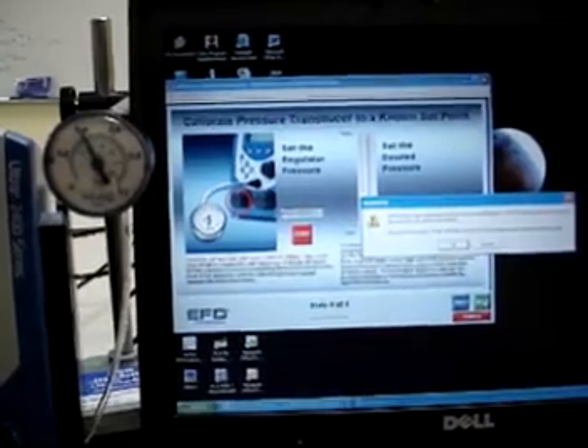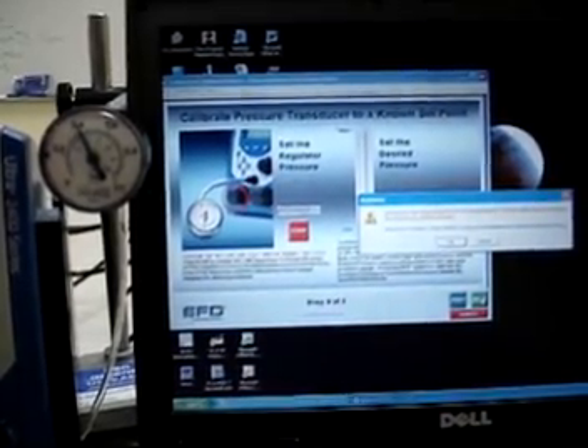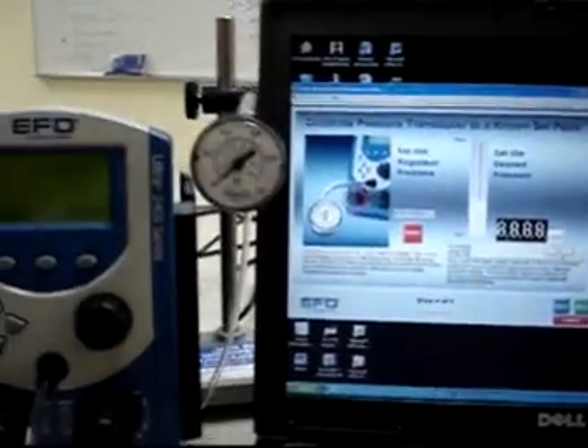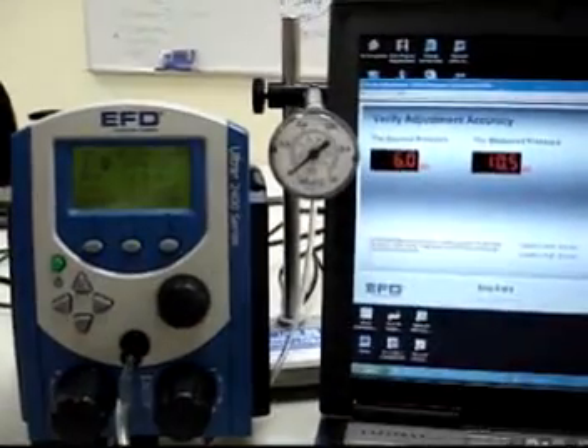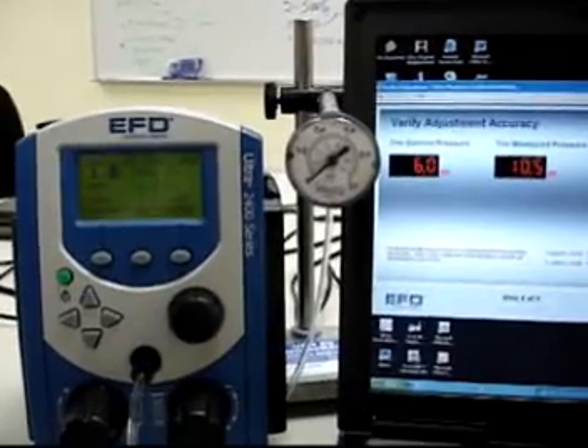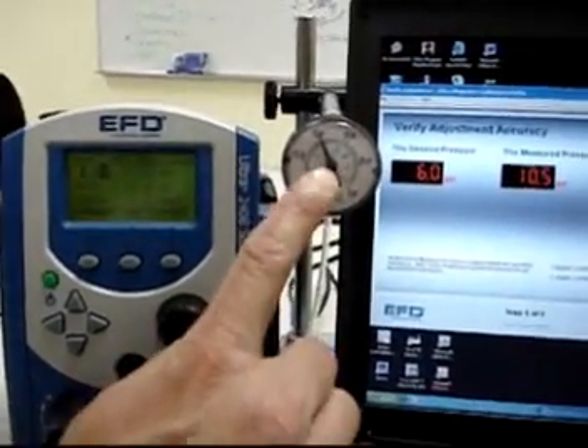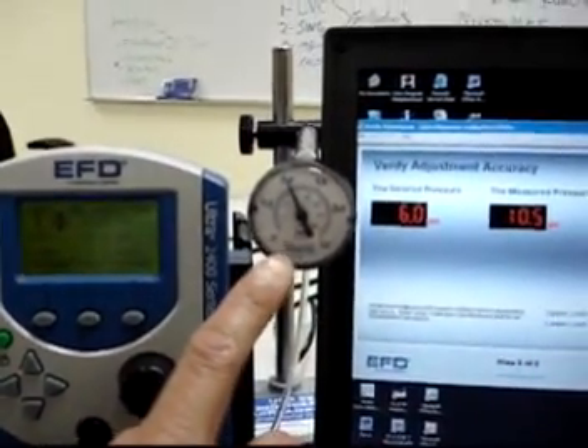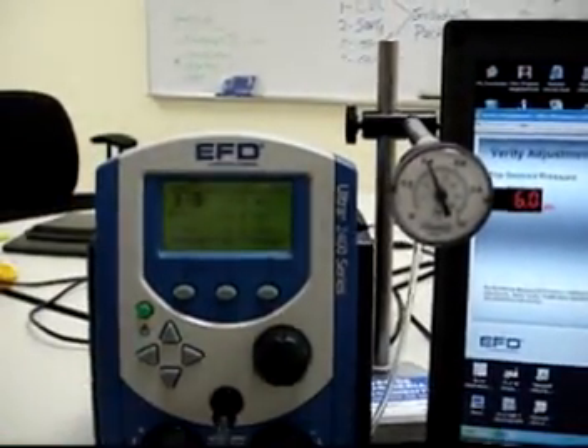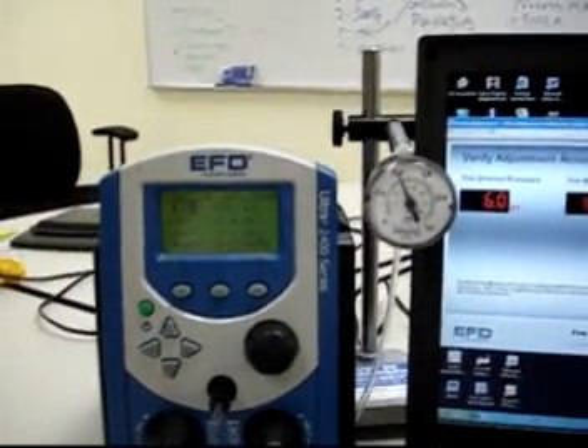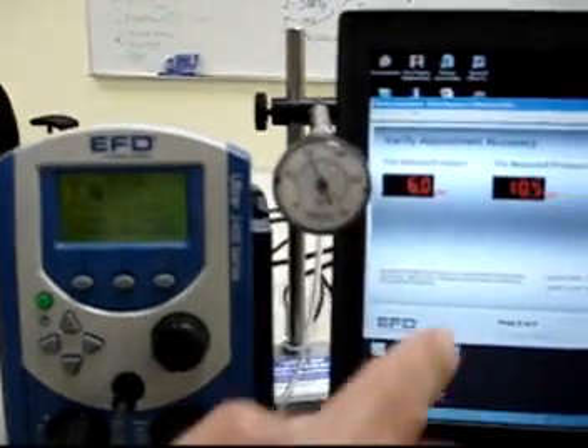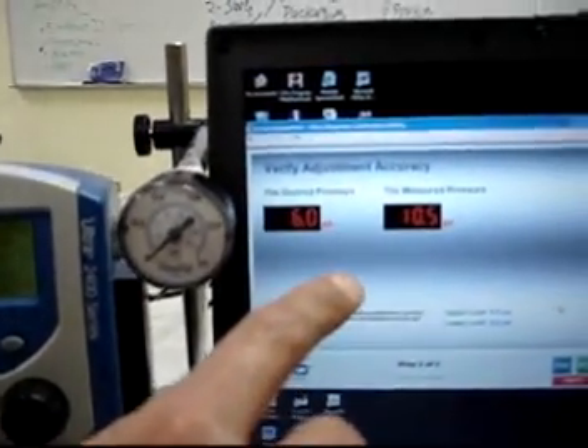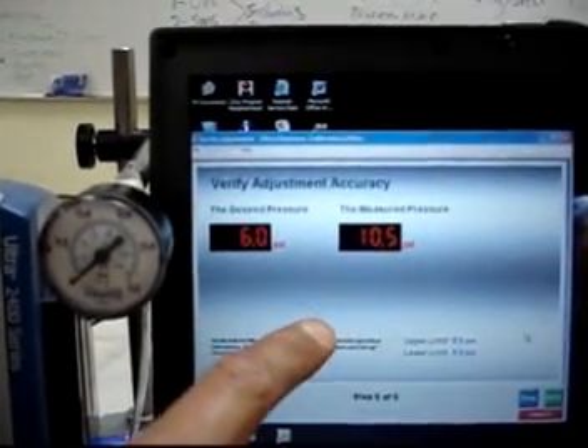The transducer will have the adjustment done. I say OK. And now we have 6 psi on my calibrated gauge, but the machine is telling me 10.4. The measured pressure, it says 10.5.